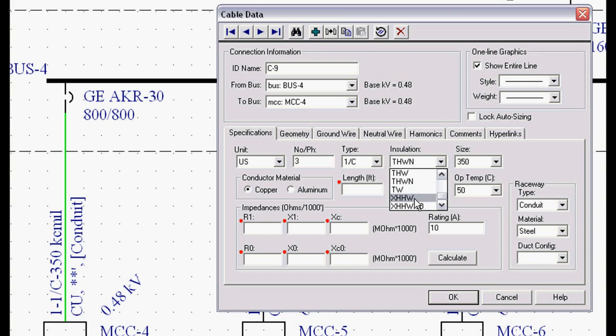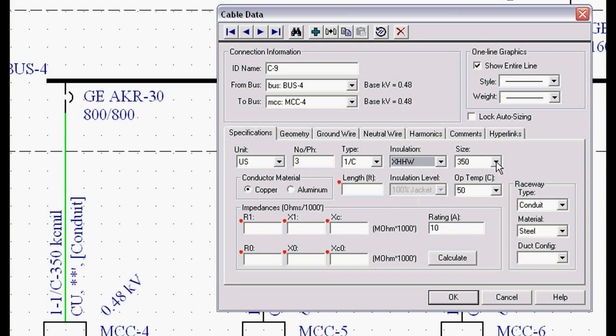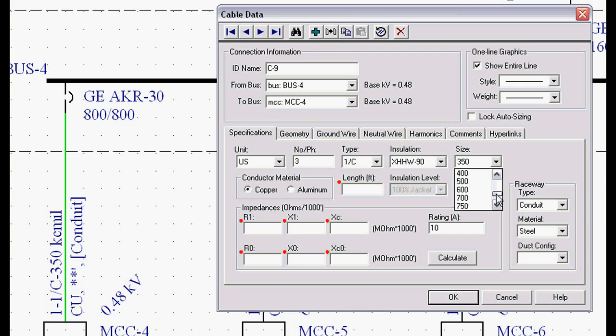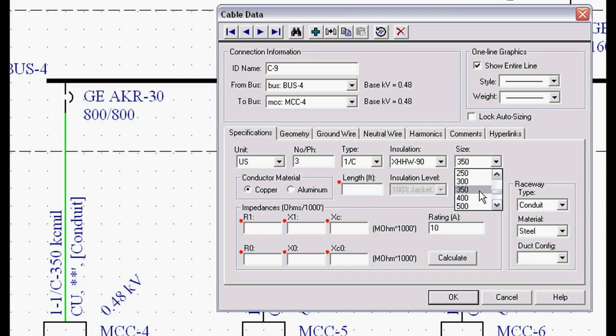If you're doing high-voltage or medium-voltage conductors, the insulation parameters change, and then you get shielding tapes and things like that that are available. Actually, we'll pick a 90-degree C there. Any size from 2,000 kcmil to 14 AWG and in between. Or you can have metric sizes, Canadian sizes, which kind of mix things sometimes.